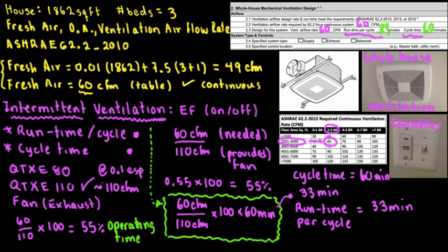Static pressure means the resistance. In other words, if you installed very well, you put your 6-inch flex duct that is connected here, and you connect this very well with the flex duct to outside, through the wall, and it's connected outside very nicely like that, you're going to have this 0.1 static pressure at 110. However, usually it doesn't work that way.